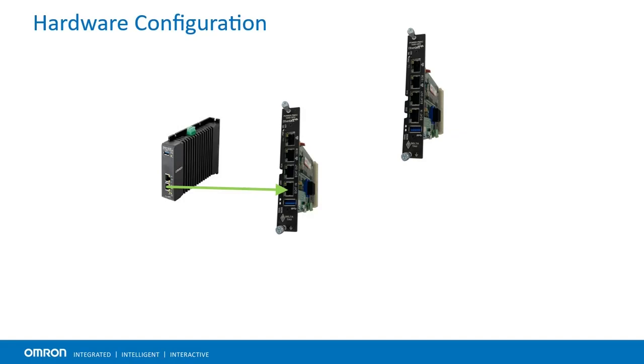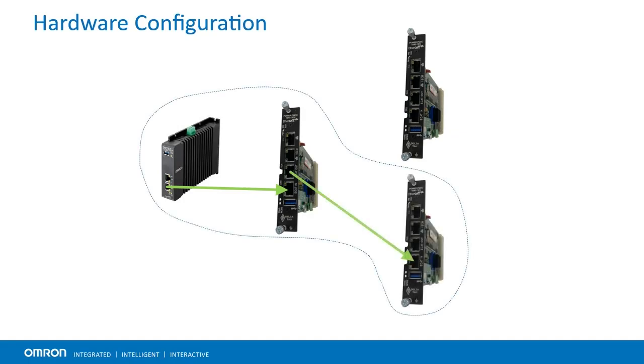The third port is the EtherCAT Slave OUT port. You can use this to connect to any subsequent EtherCAT Slave devices. Because the 1040 CPU can also be an EtherCAT Master on its own, if you prefer, you can connect EtherCAT Slave devices to the EtherCAT Master port instead.